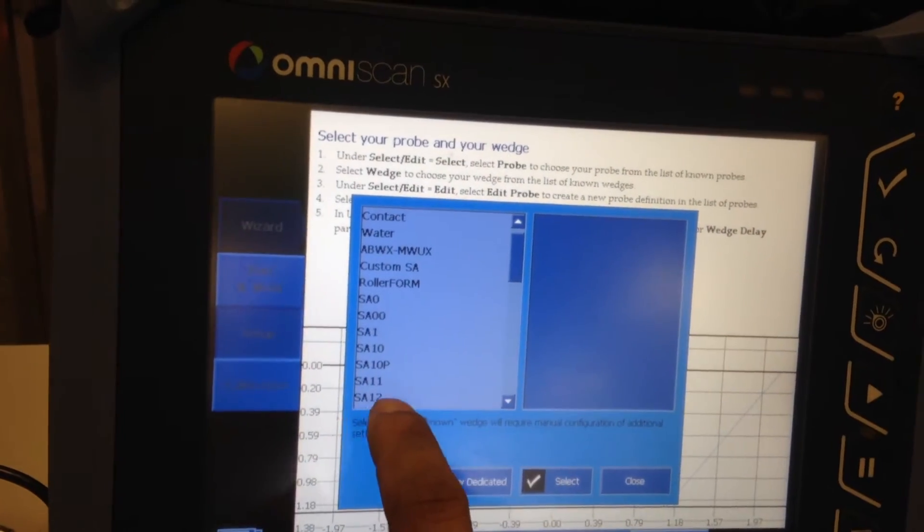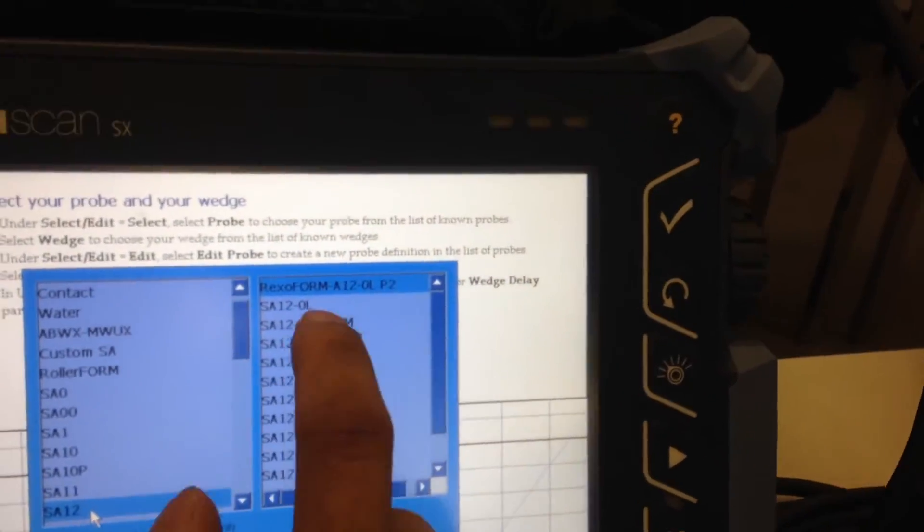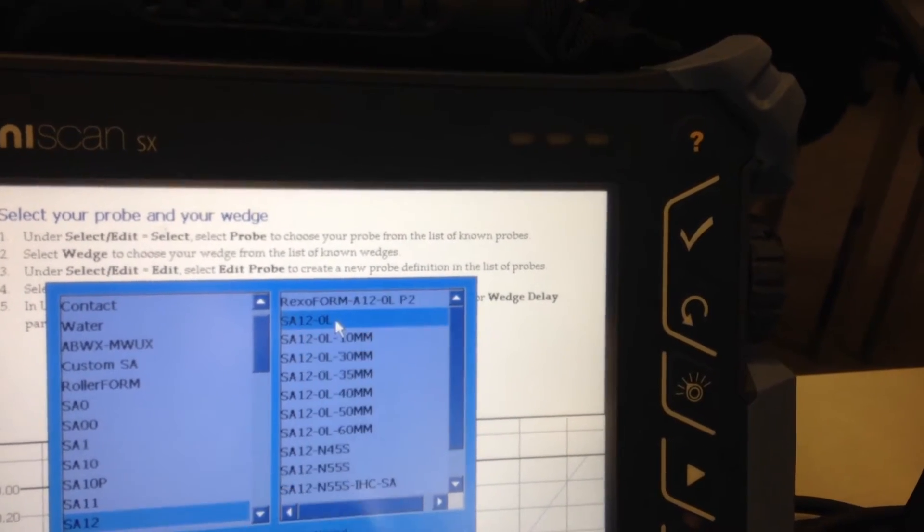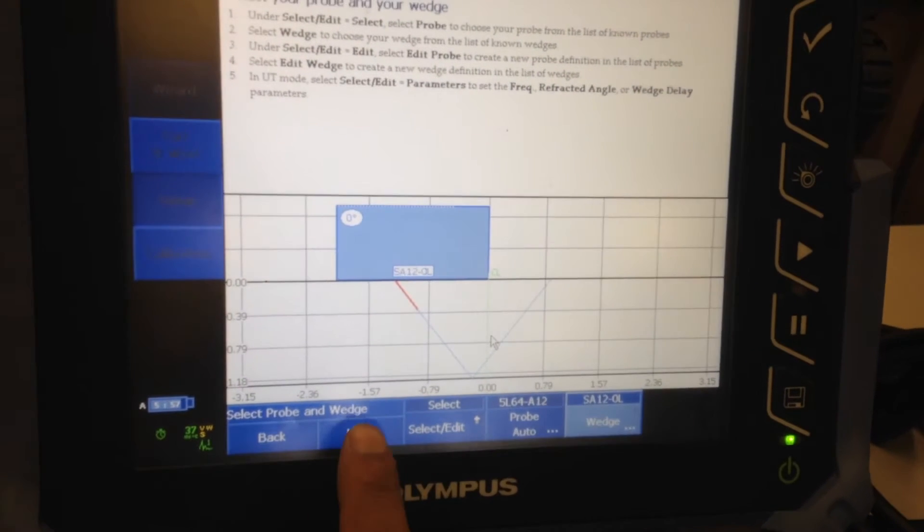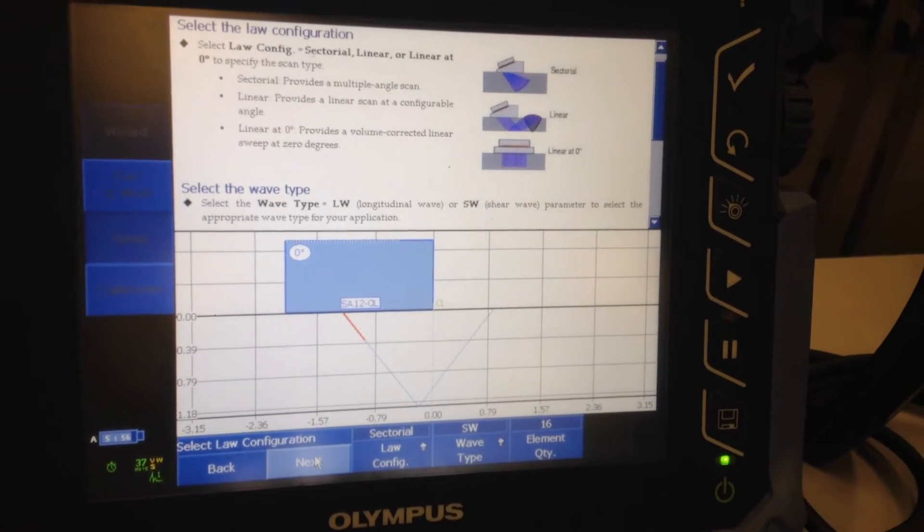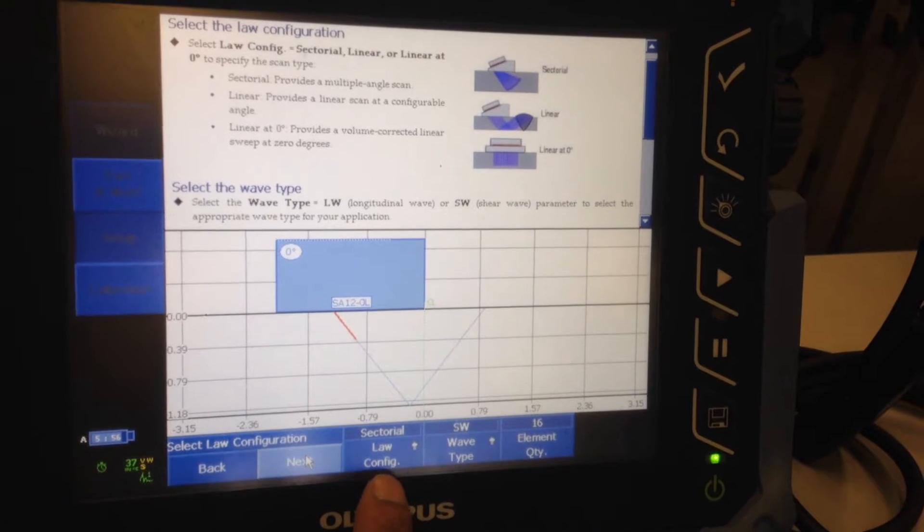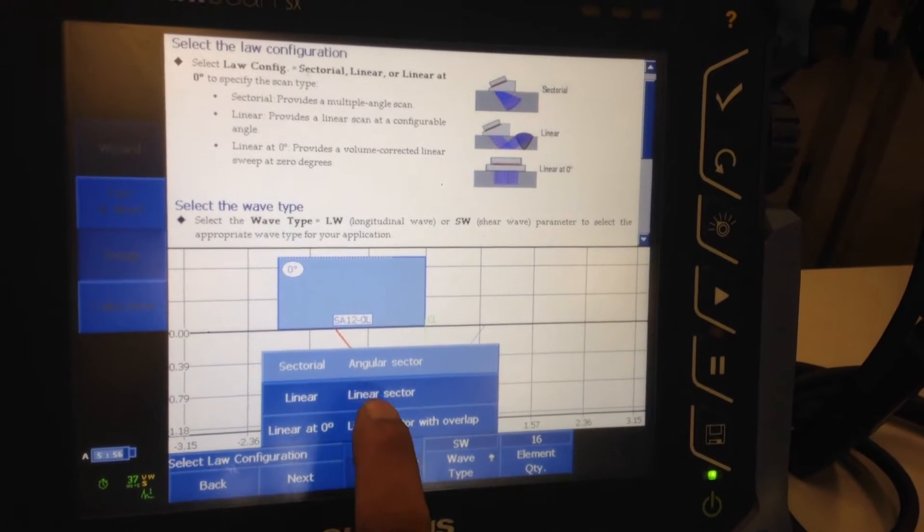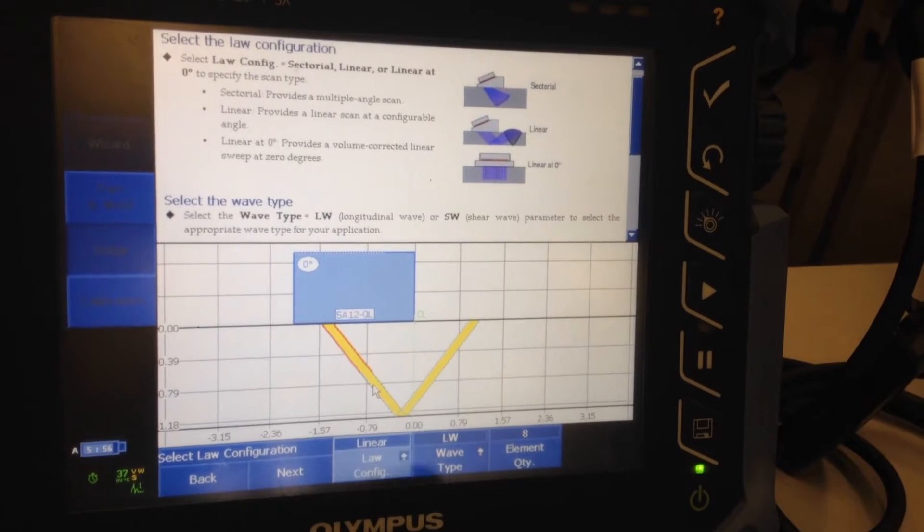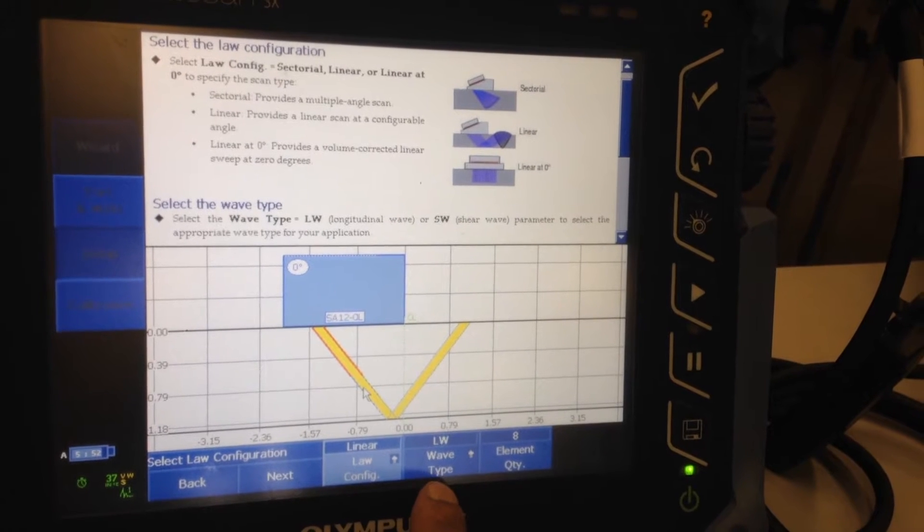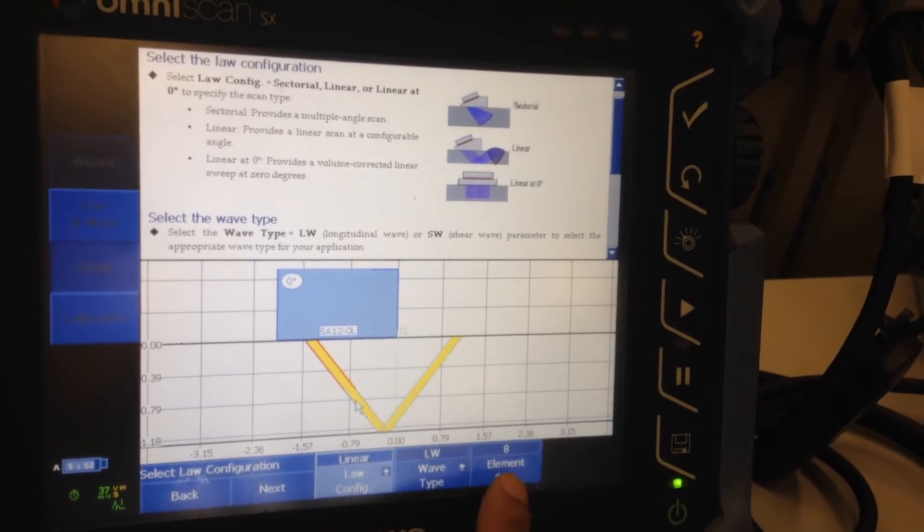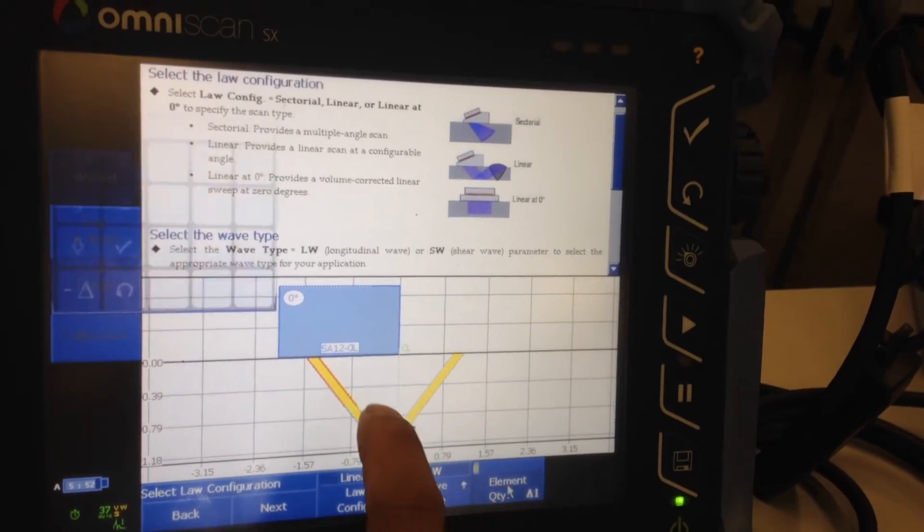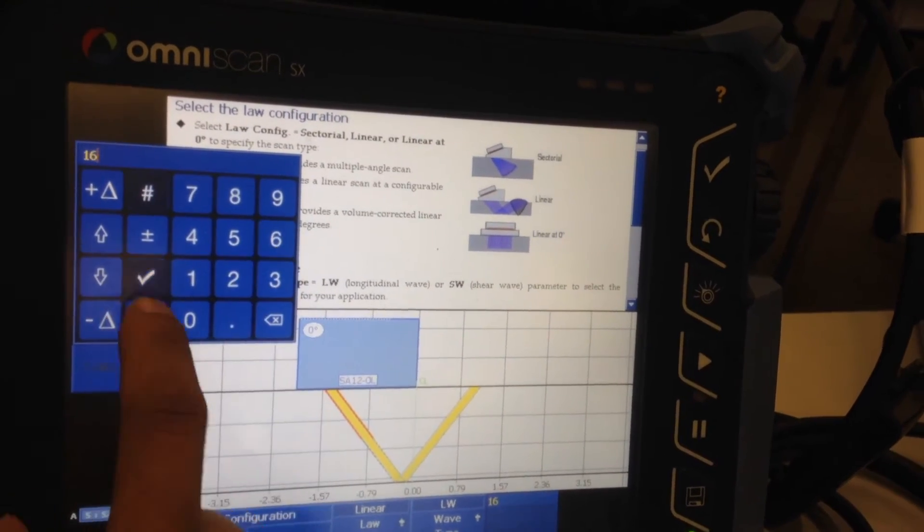Law configuration, leave it on linear. Sector type of wave longitudinal. Element quantity is eight. I can use the maximum allowed by my instrument, which in this case has 16 pulsers, so I keep my element quantity on 16. Click next.